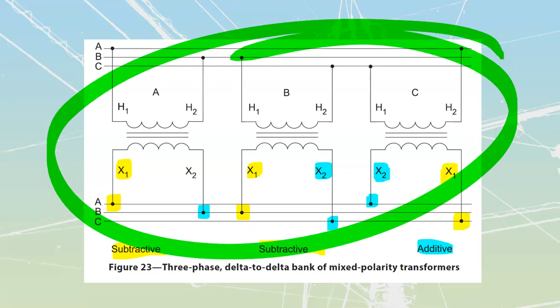The last thing we're going to talk about is my closure tests and my potential for faults on a delta bank. One of the very last things I'm going to do on a delta bank is a closure test. That's going to tell me whether I've screwed things up badly or whether I'm safe to fully energize it. My delta transformer bank will be completed except for the very last connection.